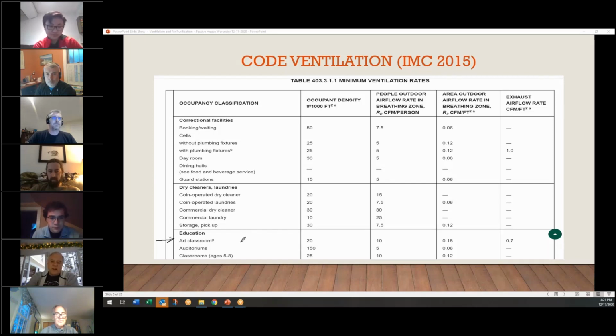And then 0.12 CFM per square foot. So they actually have two measures there. It's not just that you can have a 900 square foot room and say, well, there's only going to be one person in it, so I only need 10 CFM. You actually have to account for both the square footage of the room and the occupancy of the room in your ventilation numbers. And this is airflow in the breathing zone, and we'll get into why that's an important statement in the next slide. That's the amount of outside air in the breathing zone, which is basically from 6 feet down within the room.